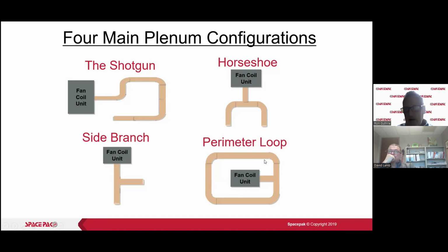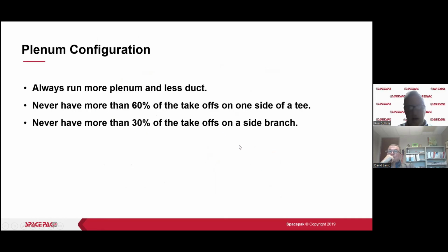Horseshoe is very common. We've got 2 branches on each side, and we've got some rules that go along with all of these. Here we're going to talk about the 60-40 rule for T's. Side branch, we've got what we call the 30-70 rule. You're not going to get any more than 30% of the air to go down this side branch. And perimeter loop, the great thing about this, if you can use it, the pressures equalize, and it's not so critical as to what you have on this T. So we can kind of throw the 60-40 rule that would be applicable for the horseshoe in the trash because we're equalizing the pressure all the way around that loop.